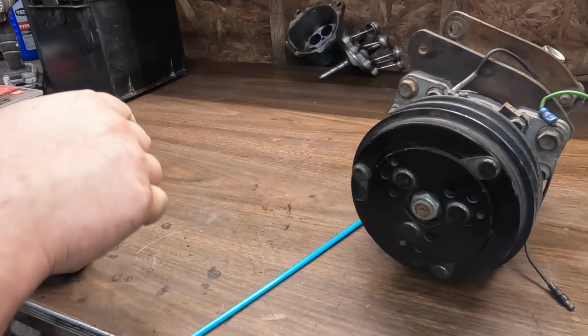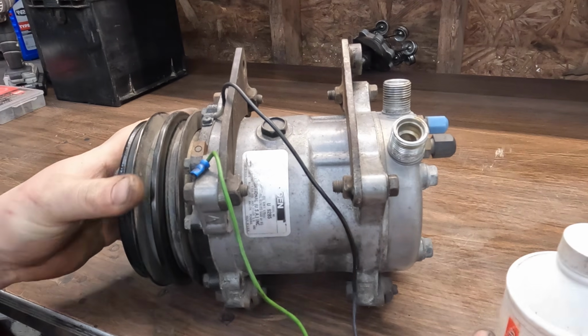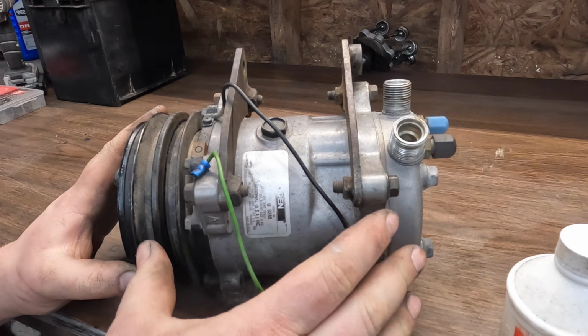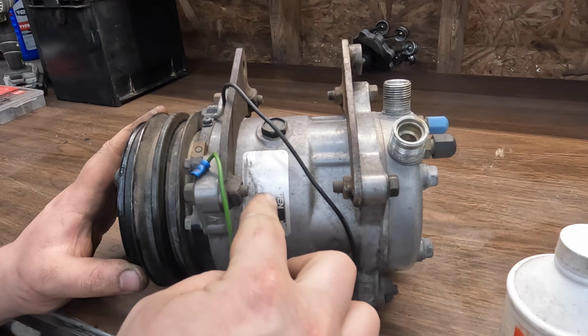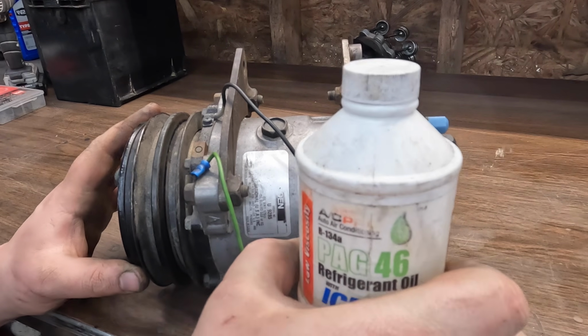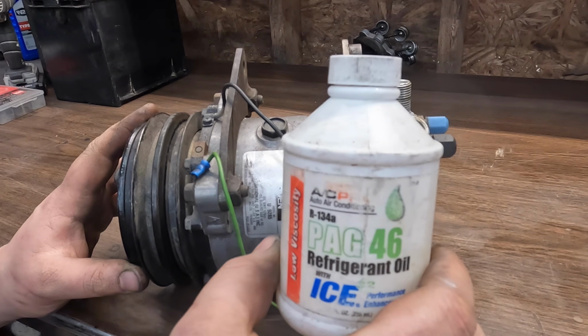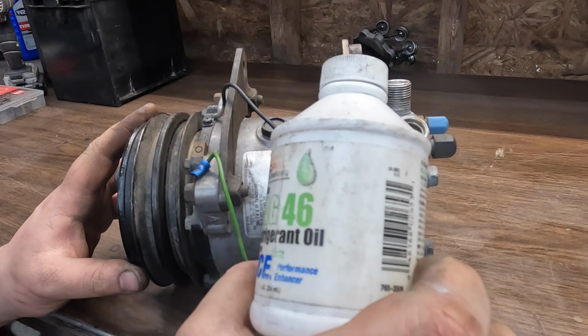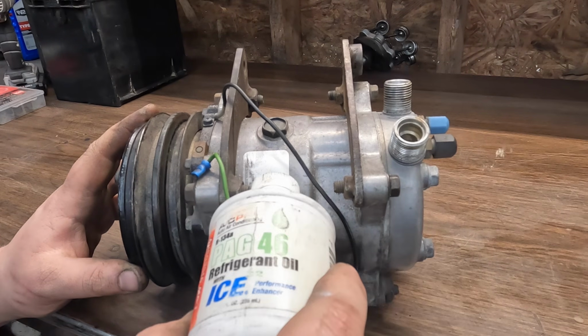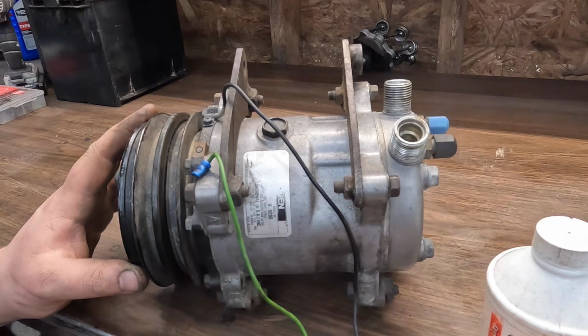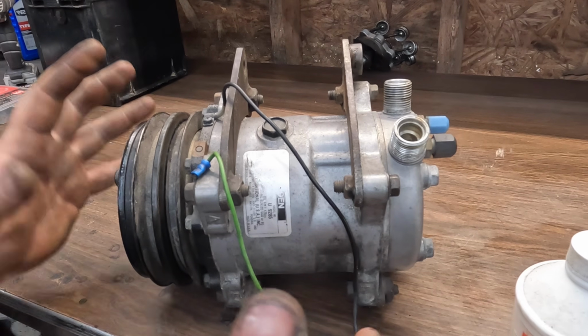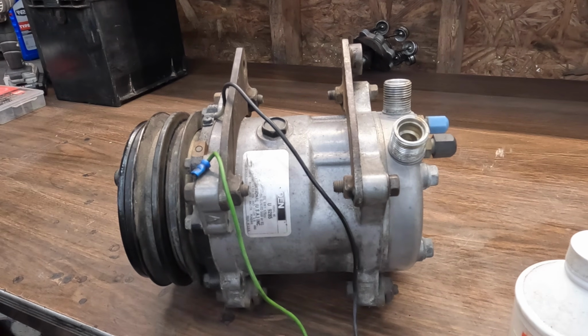Good enough. But quickly, a word on oils. Earlier R12 systems use a simple mineral-based oil. R134a systems need PAG oil, or polyalkylene glycol. Mineral oil is not soluble into 134a, so it needs its own special stuff, and you don't want to mix them - they're not compatible at all.